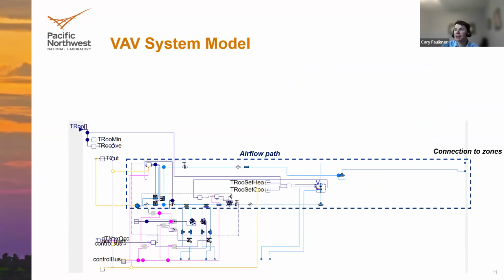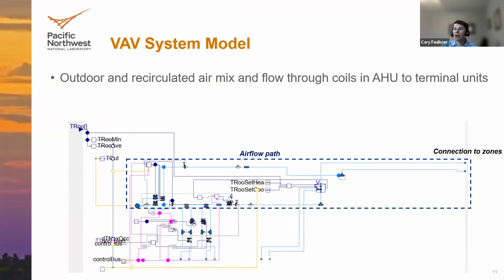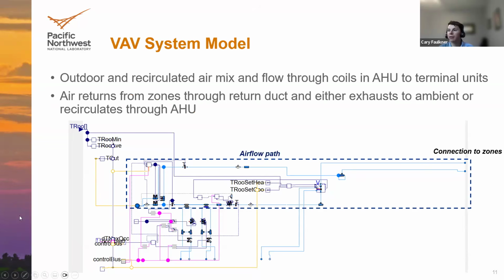So let's start by breaking this down, because these Modelica models could be a little messy, but the first key aspect is the airflow path. I mentioned in the modeling objectives modeling the airflow physics. And so this is going to include a path between the outdoor recirculated air, then being supplied to the zones, and then returning back through the air handling system. So in the bottom left corner of that airflow path is going to be your outdoor air source to draw in outdoor air and your mixing box to mix the recirculated air. And then it's going to pass through these coils and have the fan draw and move that air through the supply duct and then connect to the zones on the right hand section of that figure.